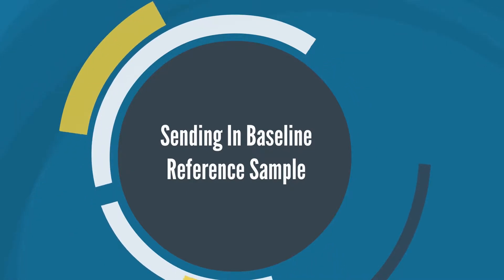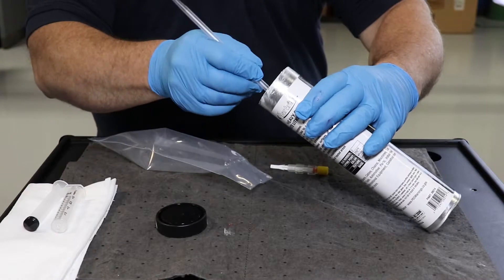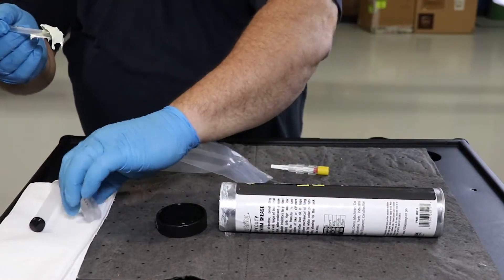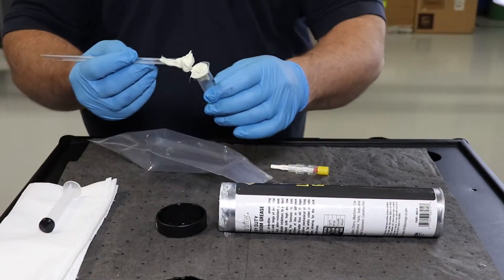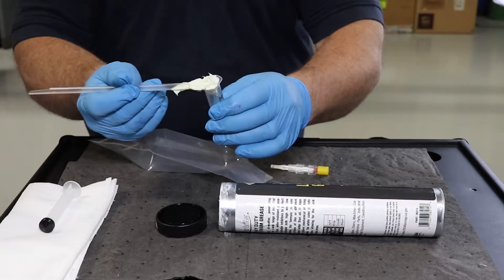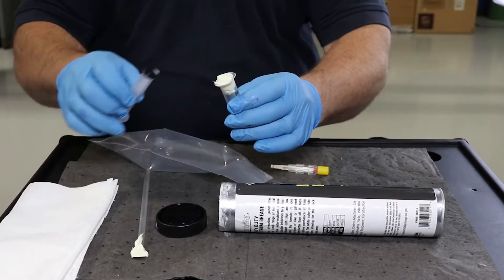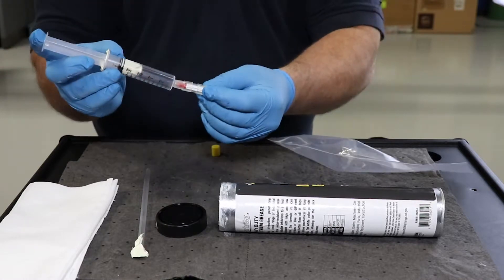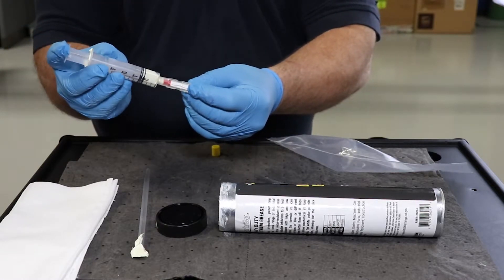For proper analysis, one baseline reference sample of new grease is required for every type of grease sent to the laboratory for analysis. This will allow us to compare the results of the new grease to the used grease to provide a more accurate analysis and an improved reliability and maintenance recommendation.